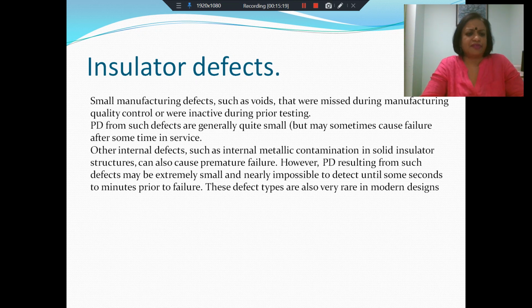You can have other internal defects also, like internal metallic contamination in solid insulating structure, embedded metallic particles, or protrusions on the conductor. All these can cause premature failure. They will cause PD, but this PD may not be very easy to detect or locate at the stage where we can take corrective action. Some can be done.